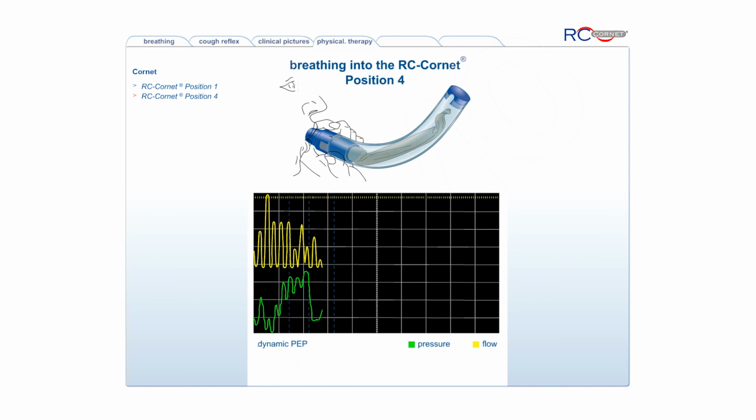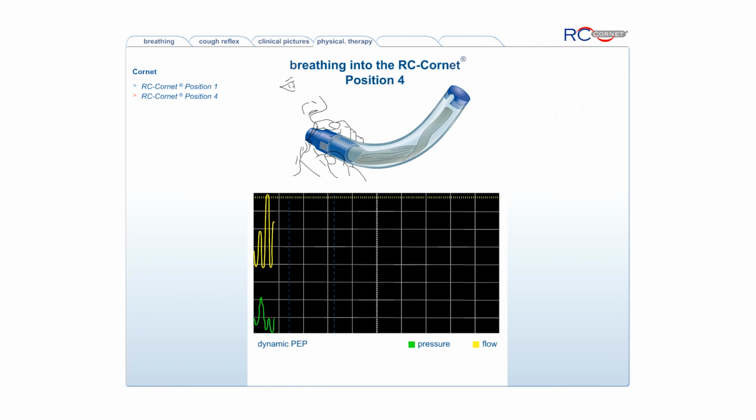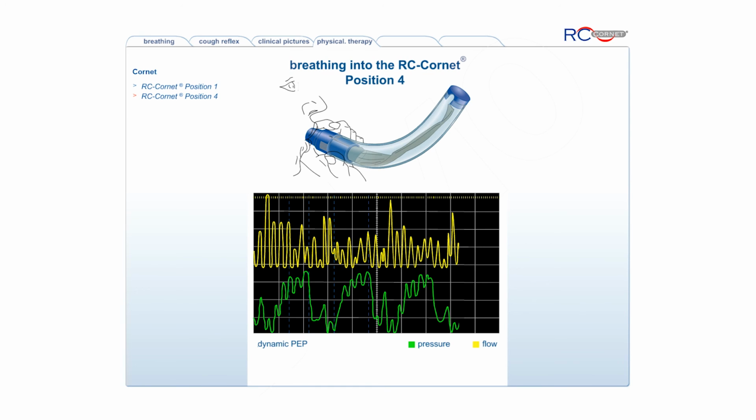Green shows the gradual increase of pressure followed by a sudden drop. The pressure and flow fluctuations, shown in yellow, are transferred into the bronchial system and lead to a gradual extension of the bronchi. This allows the mucus to reshape itself, followed by a sudden pulling together of the bronchi. The bronchial mucus does not have time to deform and is thus transported towards the mouth.